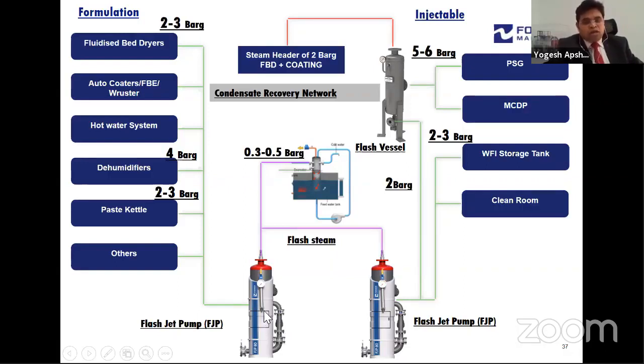It also comes with a condensate recovery meter mounted on it, which can give a 4 to 20 milliamp signal and connect to your centralized SCADA or DCS, showing how much condensate is recovered. We can have a steam flow meter on the boiler, which shows how much steam is going into the plant, and condensate recovery meters on all the condensate recovery applications, showing the condensate recovery factors and what the losses are.